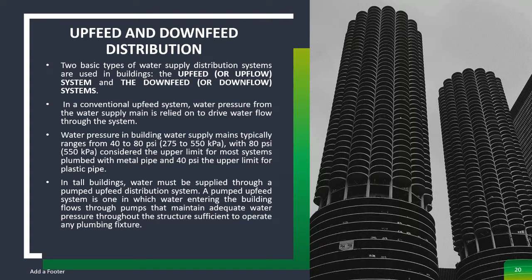In tall buildings, water must be supplied through a pump upfeed distribution system. A pump upfeed system is one in which water entering the building flows through pumps that maintain adequate water pressure throughout the structure sufficient to operate any plumbing fixture.